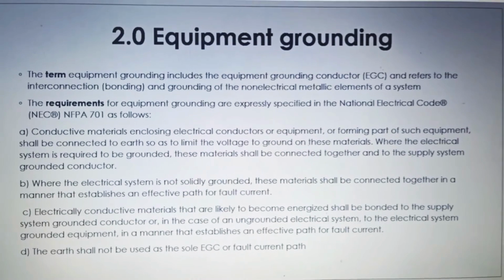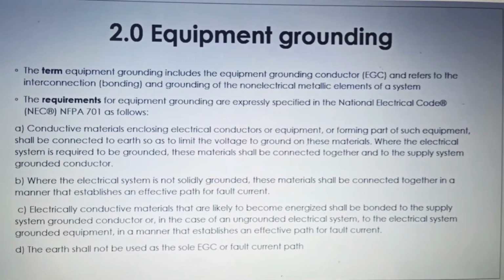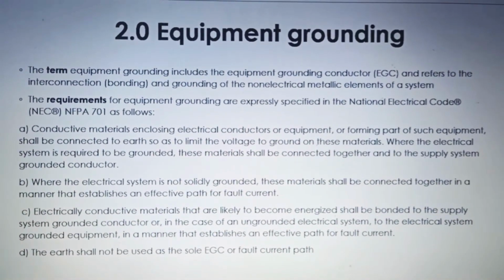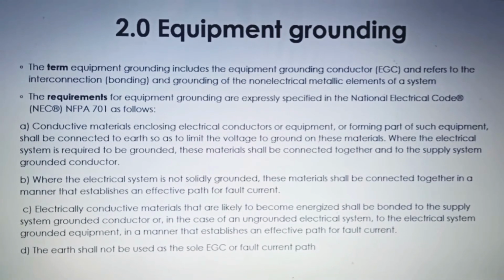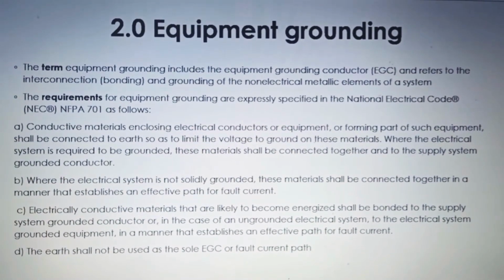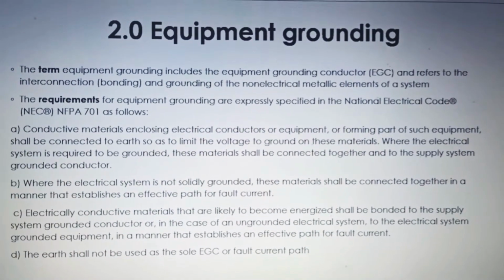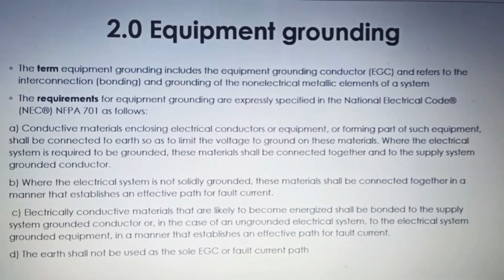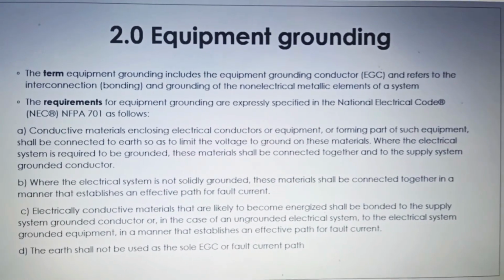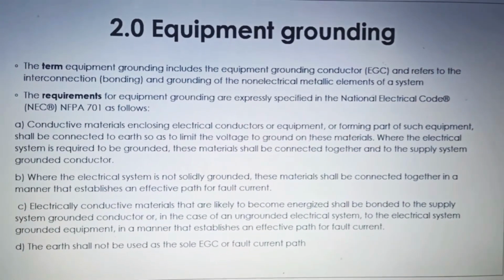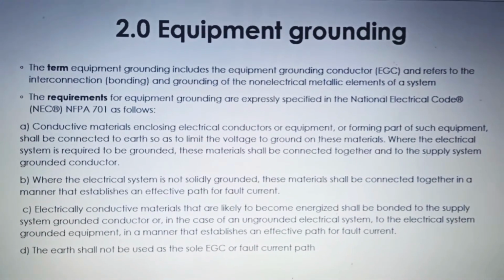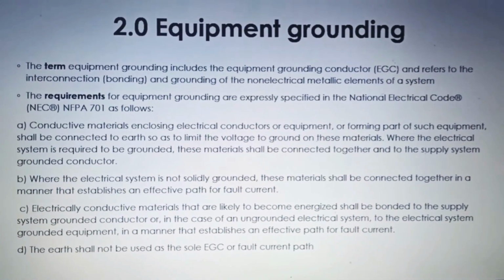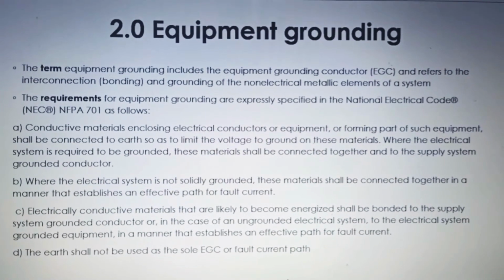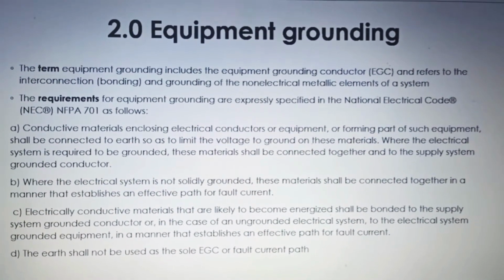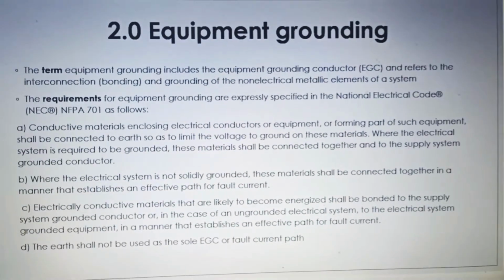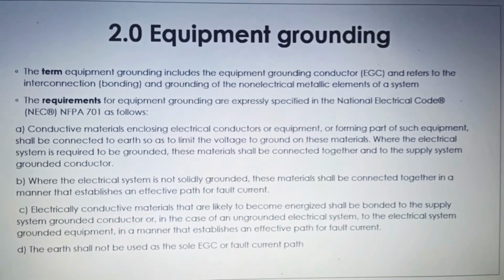Okay, we are here in chapter 2, which is equipment grounding. The term equipment grounding includes the equipment grounding conductor and refers to the interconnection, bonding, and grounding of the non-electrical metallic elements of the system. The term covered in chapter 1 may include and is part of the power distribution system. The need for an EGC exists for high impedance, low impedance, and effectively grounded systems as well as ungrounded systems. Examples of components of the equipment grounding system are metallic raceways, motor frames, equipment enclosures, and the grounding conductor wire.